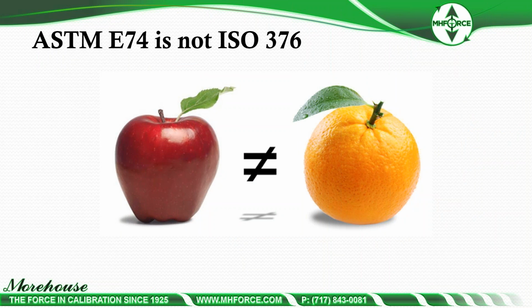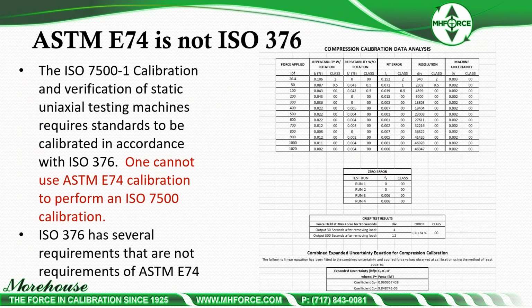I like this drawing. It is kind of comparing apples to oranges. There are similarities, but they're way too different to say I can go use an ASTM calibration to certify something to ISO 376. So the ISO 7500 calibration and verification of static uniaxial testing machines requires standards to be calibrated in accordance with ISO 376. One cannot use ASTM E74 calibration to perform an ISO 7500 calibration. ISO 376 has several requirements that are not requirements of ASTM E74.